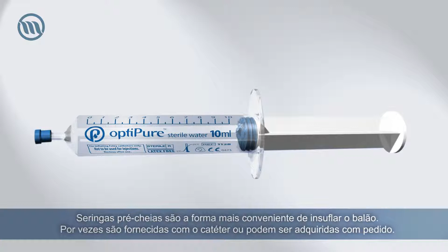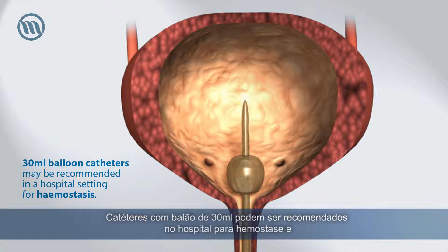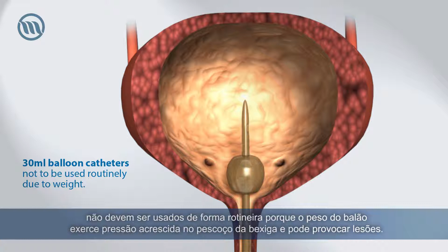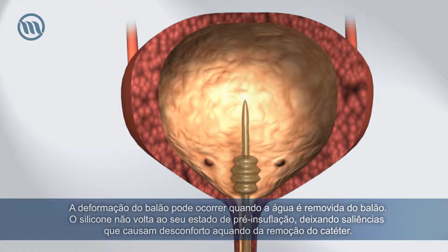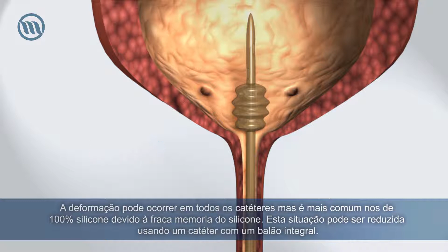Pre-filled syringes are the most convenient way of inflating the balloon. They are sometimes supplied with a catheter, or can be obtained on prescription. 30 ml balloon catheters may be recommended in a hospital setting for hemostasis, and should not be used routinely, as the weight from the balloon places increased pressure on the bladder neck and may cause damage. Cuffing of the balloon can occur once the water has been removed from the balloon. The silicone does not return back to its pre-inflated state, and instead it leaves ridges which cause discomfort on removal. Cuffing can occur in all catheters, but it is most common in 100% silicone catheters due to silicone's poor memory. This can be reduced by using a catheter with an integral balloon.